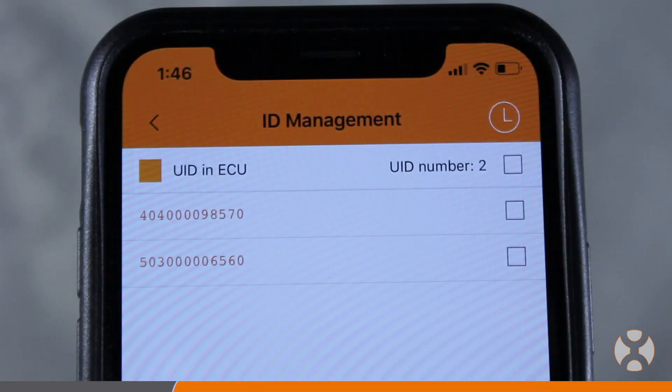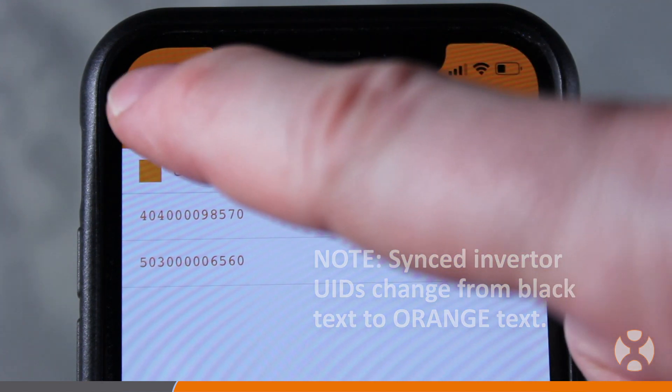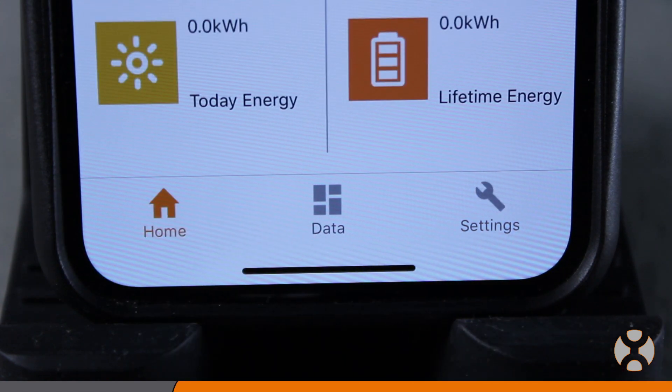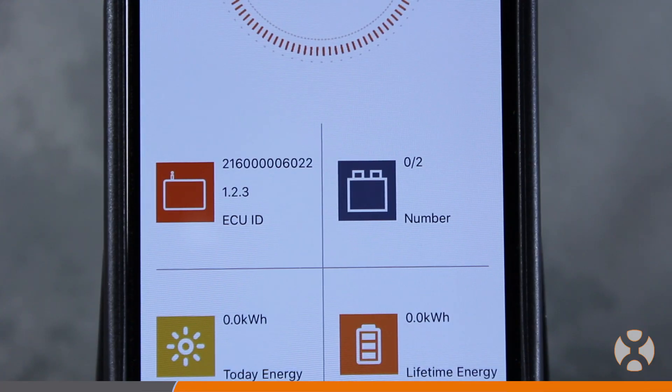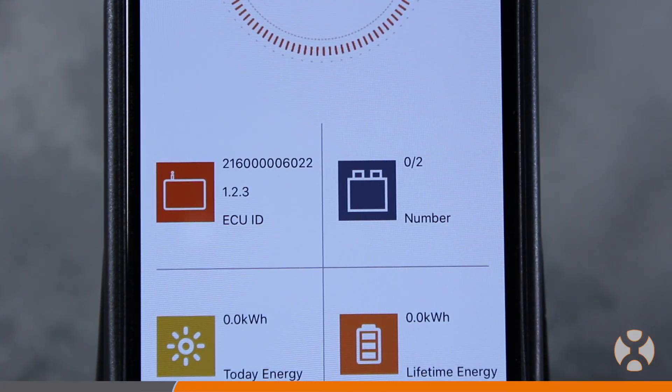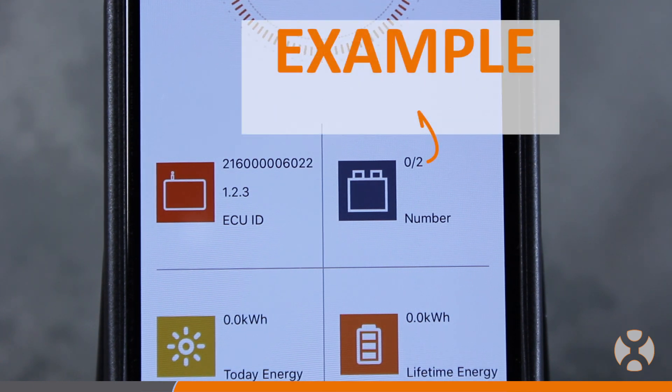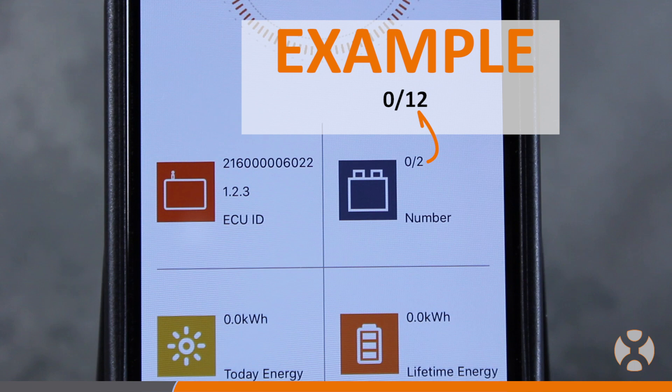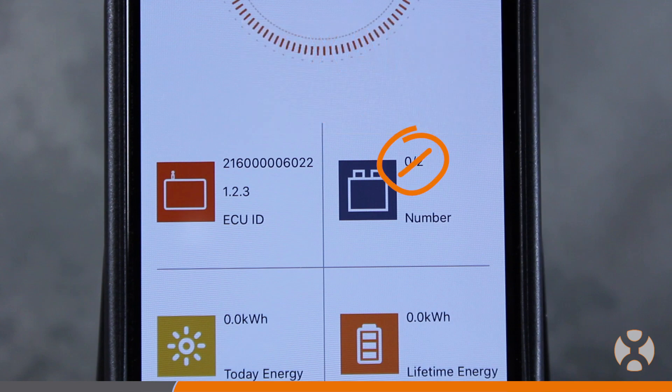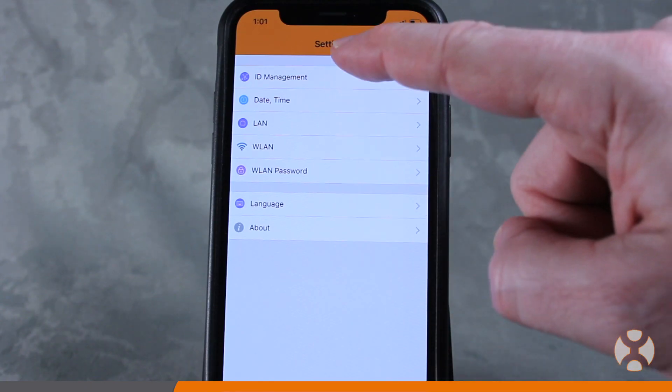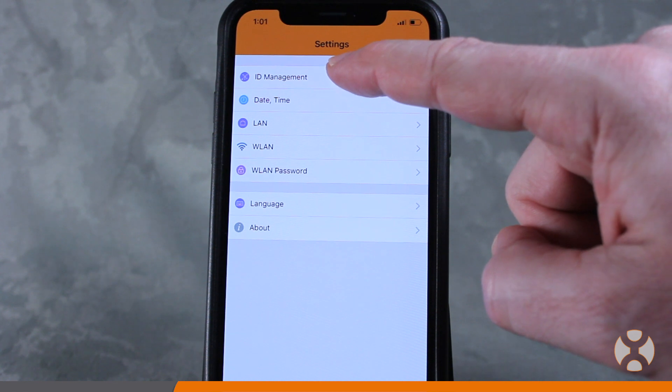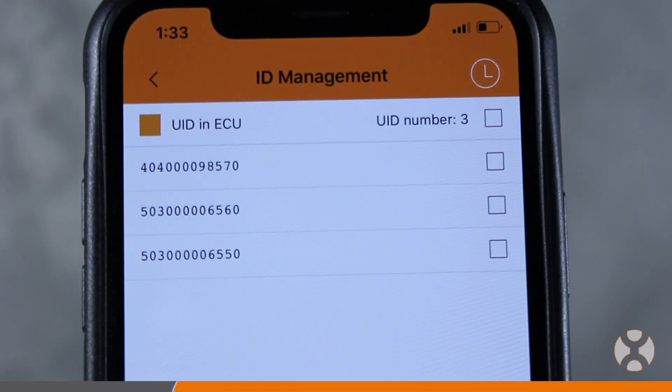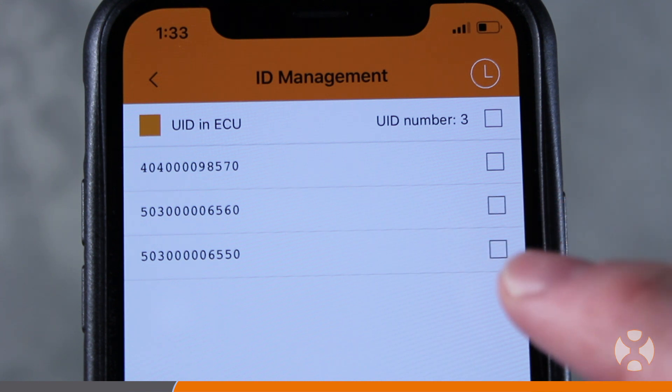After all the microinverter UIDs are synced to the ECU-R, go to the home screen and verify the number of microinverter units displayed next to the microinverter icon is correct. If you synced 12 inverters, the number 0 over 12 should be displayed here. This means 12 inverters are present with zero talking. The inverters will begin communicating once power is supplied by the solar panels. If the correct number of inverters is not displayed, you'll need to return to the ID management screen and verify the UIDs to determine which units are not present and add them.